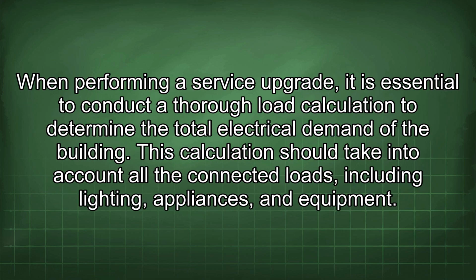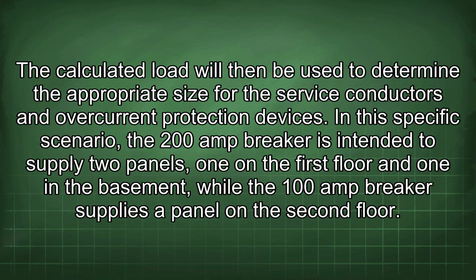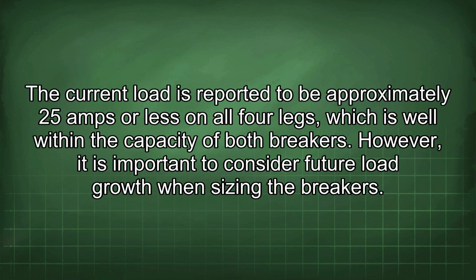When performing a service upgrade, it is essential to conduct a thorough load calculation to determine the total electrical demand of the building. This calculation should take into account all the connected loads, including lighting, appliances, and equipment. The calculated load will then be used to determine the appropriate size for the service conductors and overcurrent protection devices. In this specific scenario, the 200 amp breaker is intended to supply 2 panels, one on the first floor and one in the basement, while the 100 amp breaker supplies a panel on the second floor. The current load is reported to be approximately 25 amps or less on all 4 legs, which is well within the capacity of both breakers.